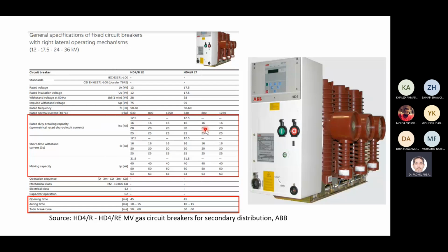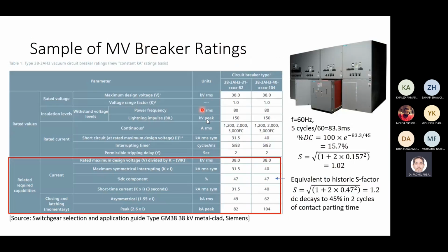فنضيف 25% higher than the short circuit current، ونختار على طول البريكنج كاباسيتي اللي هي السيمتريكال بريكنج كاباسيتي، هاي ماكسيموم سيمتريكال انتربتر كيرنت. فمثلا لو عندي 10 كيلو أمبير أضيف له 25% وأختار على طول البريكر based on the symmetrical rating، بدون ما نروح إلى تقييم إيجاد الإكس آر ريشيو، شوف السيمتريكال فاكتور and so forth.